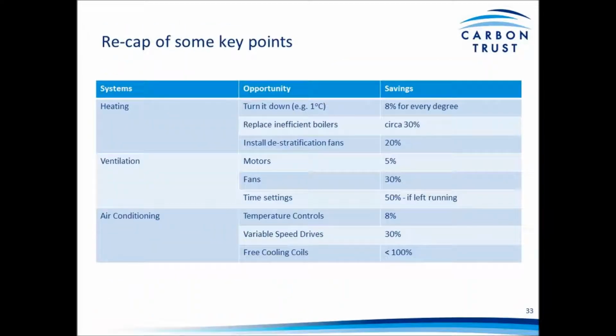And then a quick recap of some of the key points. So for heating, turn it down. Every 1 degree C, 8% energy saving. Upgrade to higher efficiency boilers could save 30%, and destratification fans to push air to a low level within high ceiling spaces can save 20%.